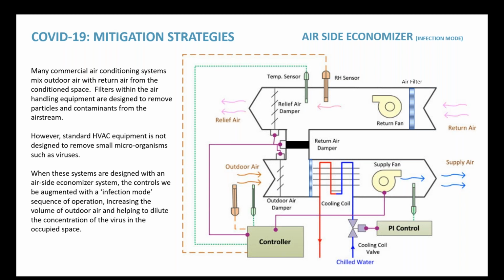So in some cases, you may have larger cooling coils, or the cooling coil has more capacity than it needs, so you can increase the amount of outside air. But all of these things need to be worked in concert with the control system for the equipment, because at some point it may become too hot outside and you need to start recirculating some and backing off the outside air to maintain comfort conditions. So this is definitely a strategy to try to deliver more outside air to the space.